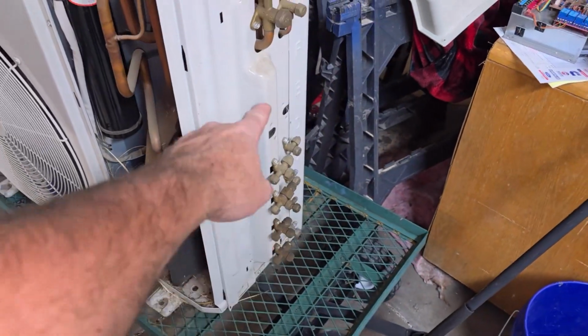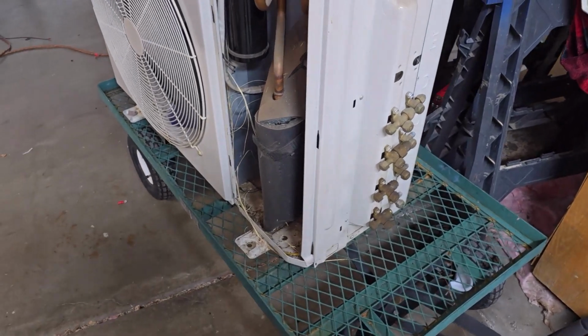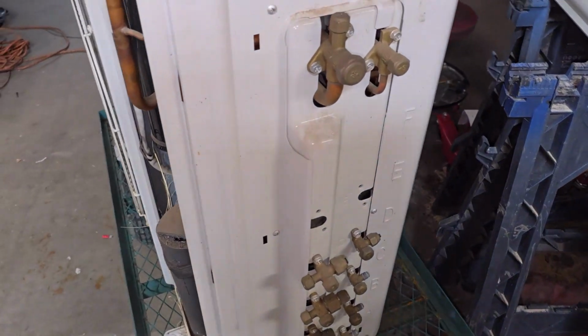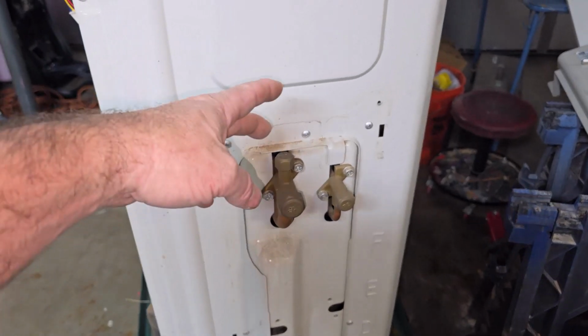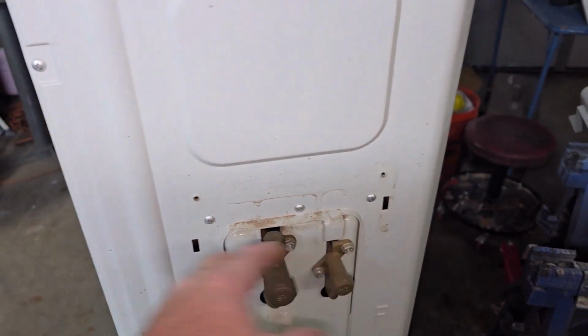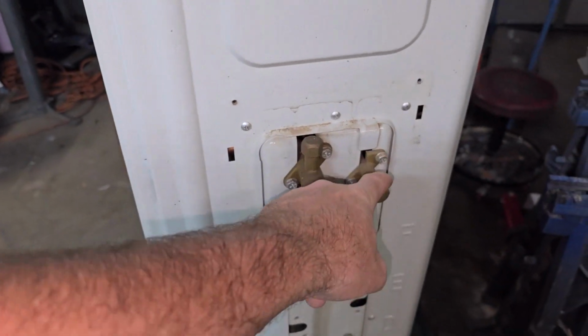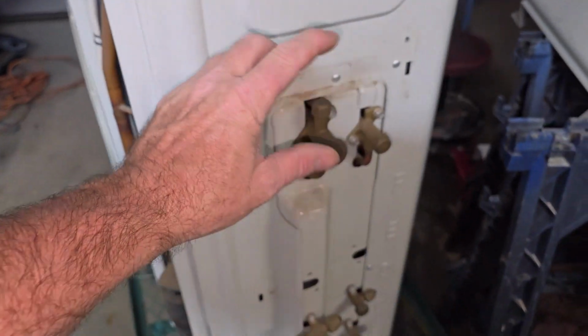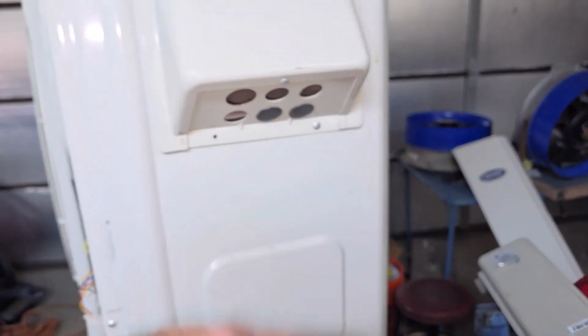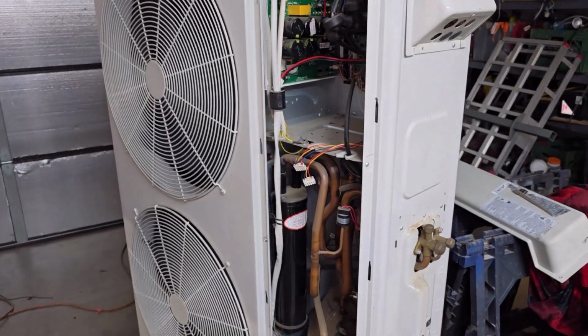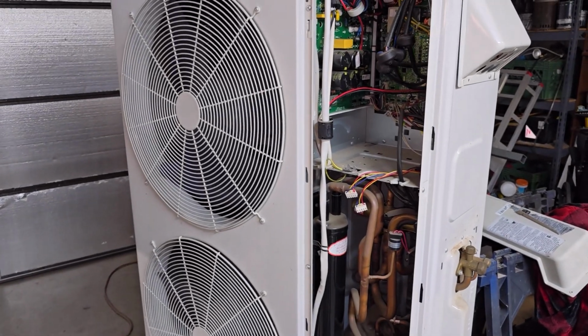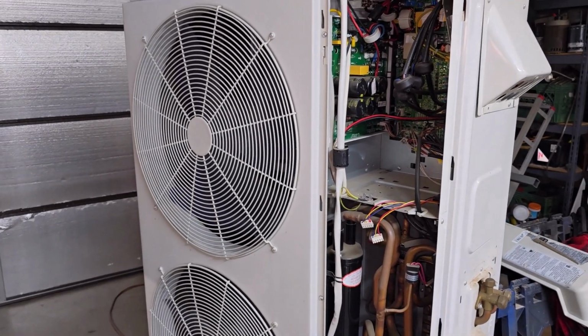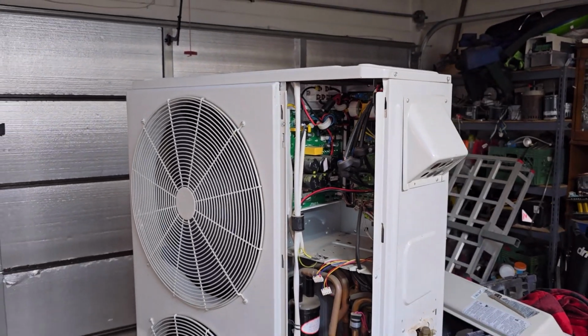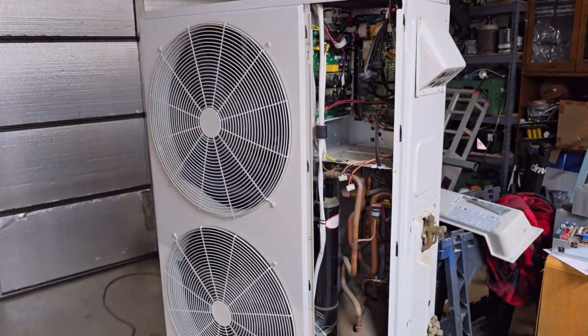Again, I'm going to pull out all this - I've already made a video where I did the identical thing. I'm going to take out the common manifolds, reuse these as just the one suction and one liquid line isolation, run the pipes down here, repurpose the coil, repipe it, put in check valves, capillary tubes for the outdoor metering device, which is working perfect for heating mode on the one I have now.